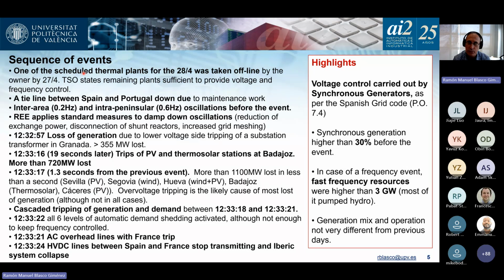So one of the technical reasons to schedule additional thermal plants is because of voltage control capability or frequency control capability. One of the plants that were scheduled was taken offline by the owner for maintenance purposes on a short notice. The TSO didn't schedule any additional thermal plant because it was evaluated that the remaining plant was sufficient to provide the security margins for voltage, frequency control, and N-1.